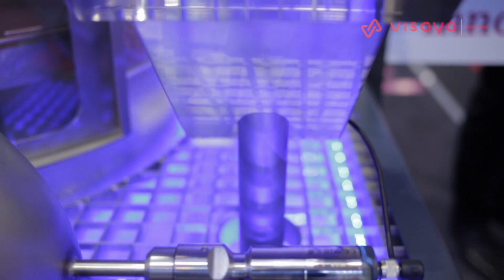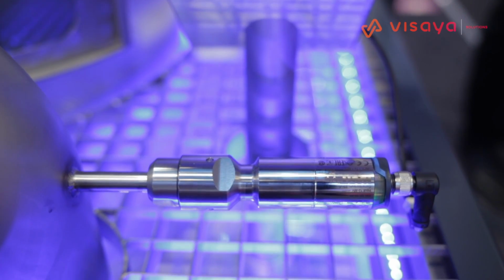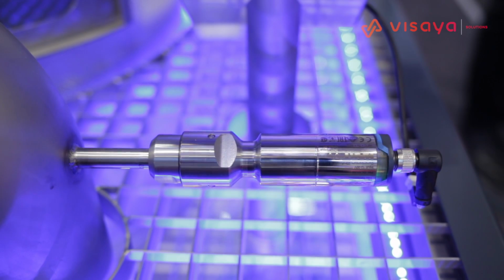It activates itself after the sterilization cycle. You heat up your plant above 120 degrees, you kill everything inside, and then you wait, because you have filled your plant, your vessels, with hot steam, and if you cool it too fast, there's an underpressure inside.